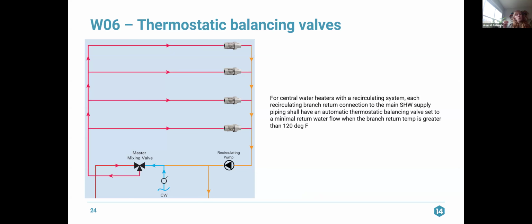So for a central water heater with a recirculating system, each recirculating branch return connection to the main service hot water supply piping shall have an automatic thermostatic balancing valve set to a minimal return water flow when the branch return temp is greater than 120 degrees. And so the idea here is that we have this thermostatic balancing valve. We are circulating 5 GPM down this branch. We don't want to be returning a bunch of really hot water into the return.